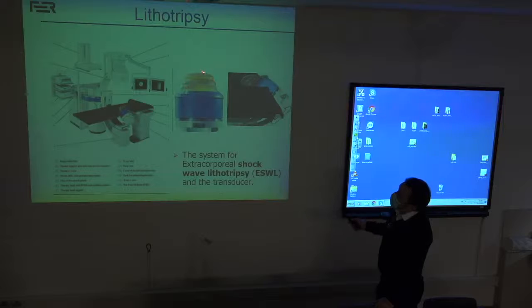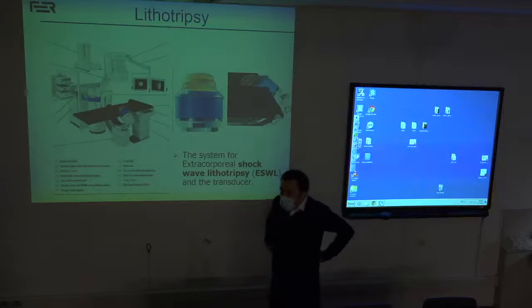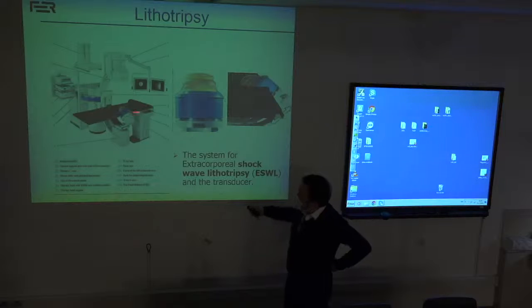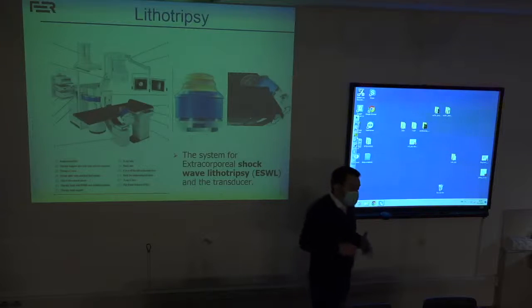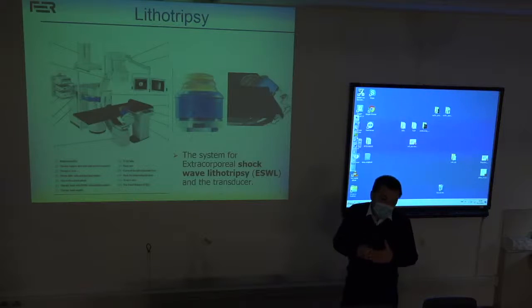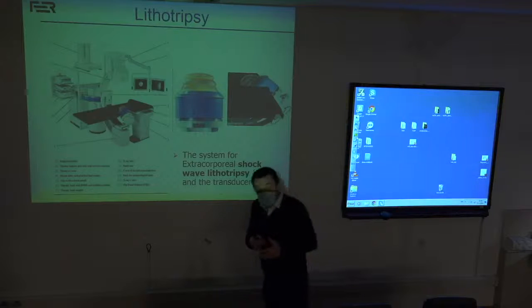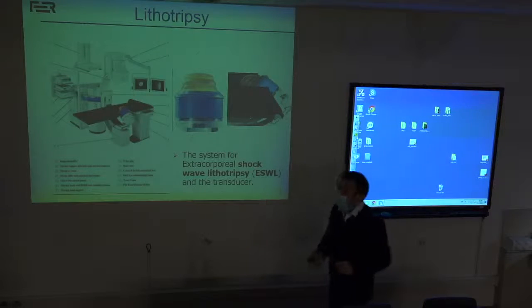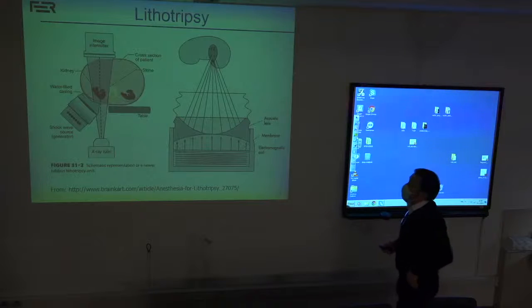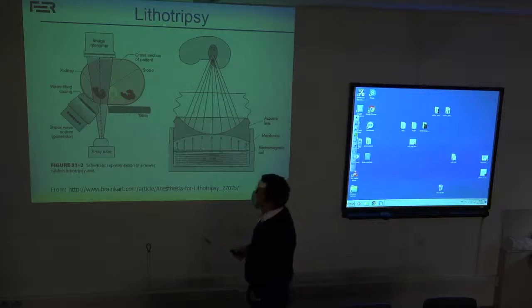So this part here is plastic, of course, and though it seems that you will be lying on this part when they put you on this table here, it still needs some kind of filling between the skin and this ultrasonic head, so that in most cases the gel is also used here, so that you have the feeling that there is no air in between. So this is, let's say, the principle of operation.